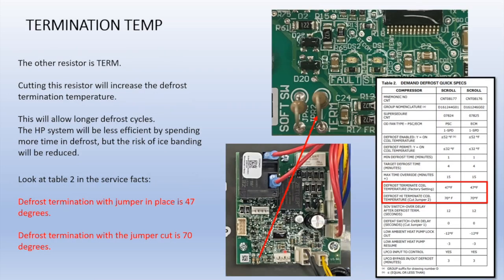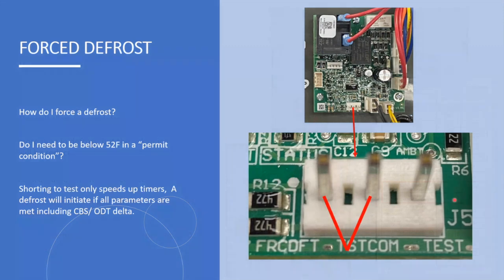Your termination temperature, we talked about how factory is 47. When you cut it, it's 70. That's the temperature that the defrost terminates at. So if you cut this, it's going to go from 47 to 70. To force a defrost, you would jump these two wires, jumpers.